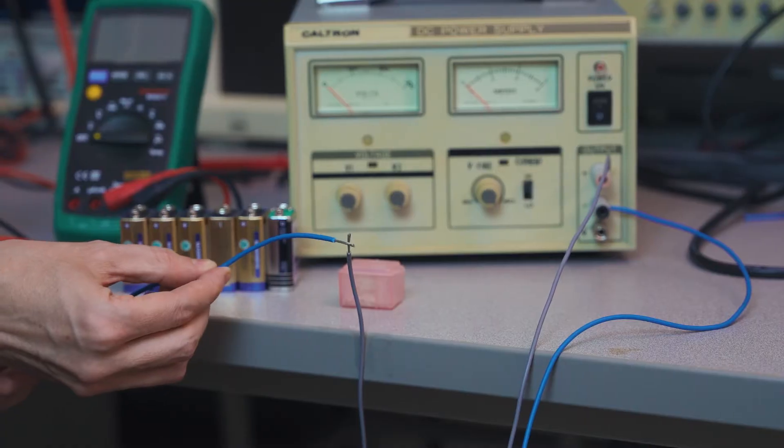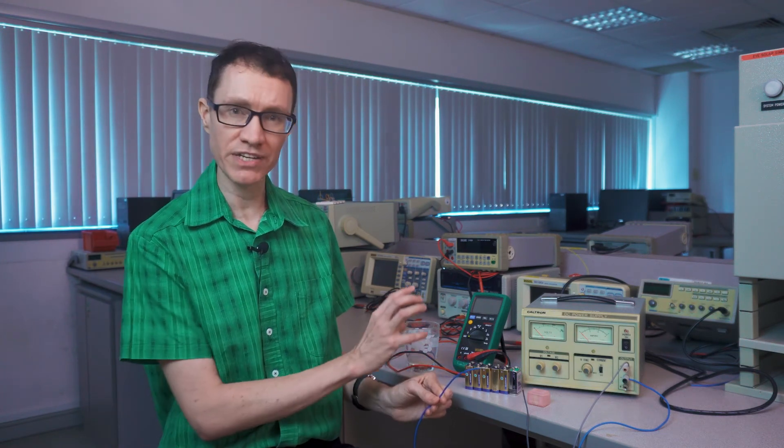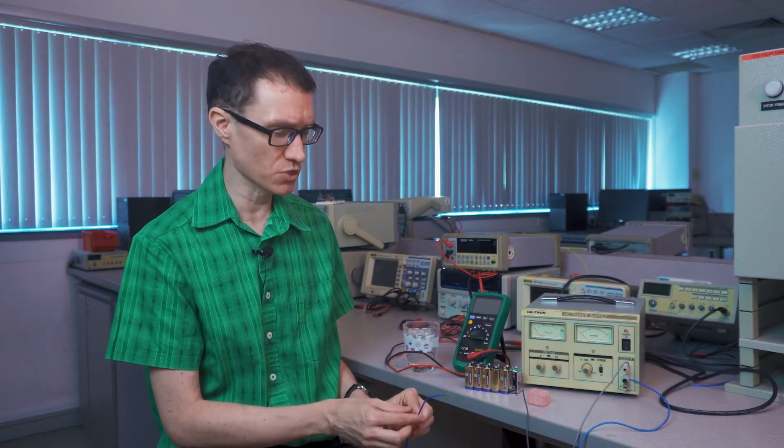I'm going to go ahead and discharge this power supply by tapping the two electrodes towards one another, even though I've shut it off. This is good practice anytime you're working around high voltage equipment because there are often internal capacitors in these power supplies that tend to be charged up. It's always a good idea to make sure they're fully discharged even though you've turned off the switch.